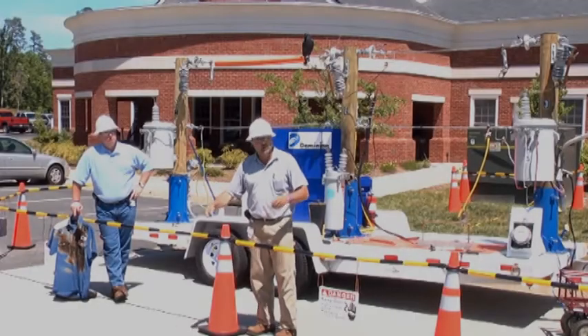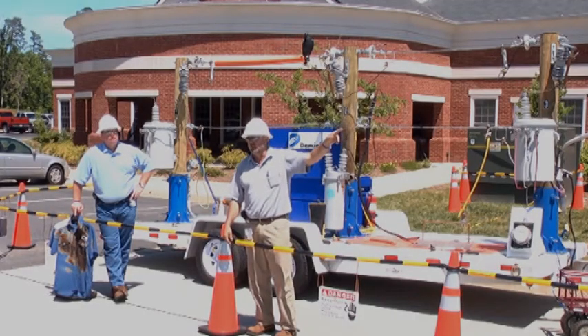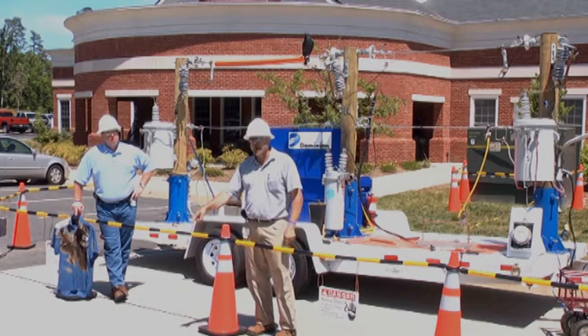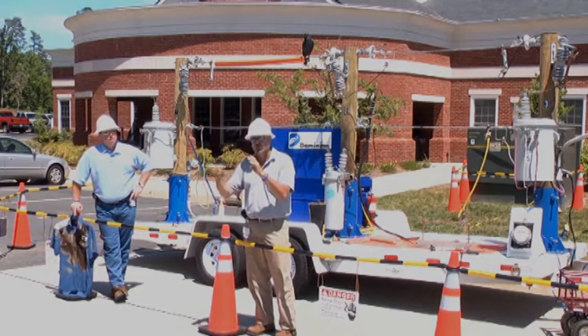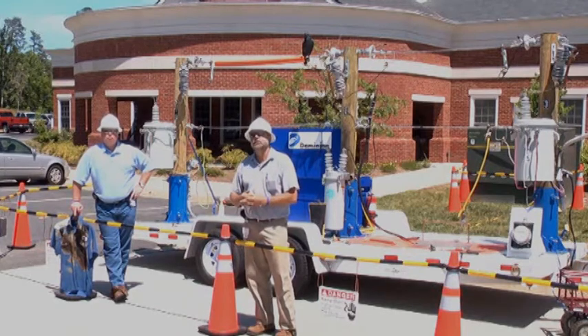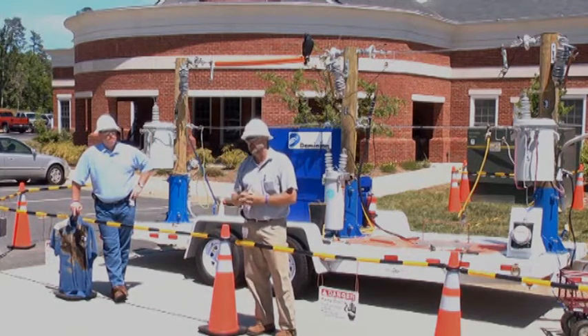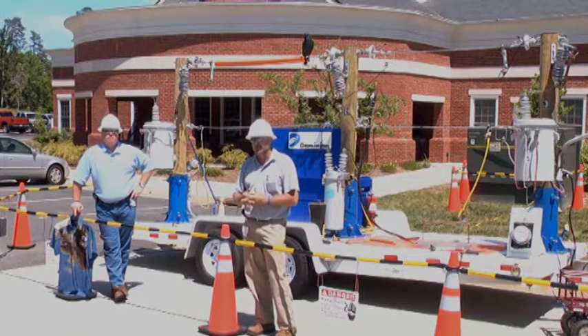You could have one phase cut. You could hear a fuse blow, but that wire would still be hot because the poles in the transformer are re-energizing the wire and backfeed. So even though you see a fuse open, that doesn't mean the lines are dead. You can still have backfeed on.